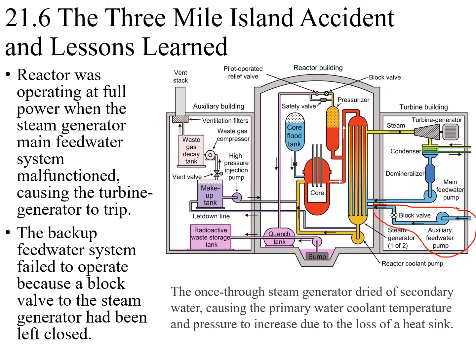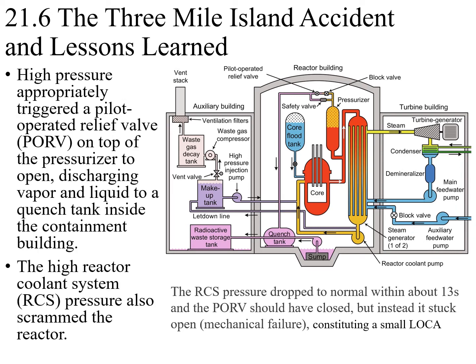Because of that, the once-through steam generator dried of secondary water, causing the primary coolant temperature and pressure to increase due to the loss of a heat sink. As planned, this high pressure appropriately triggered a pilot operated relief valve on top of the pressurizer to open, discharging vapor and liquid to a quench tank inside the containment building. As shown here, we have the pressurizer. If the primary loop pressure is too high, it will automatically open those valves and discharge the steam into this quench tank to condense.